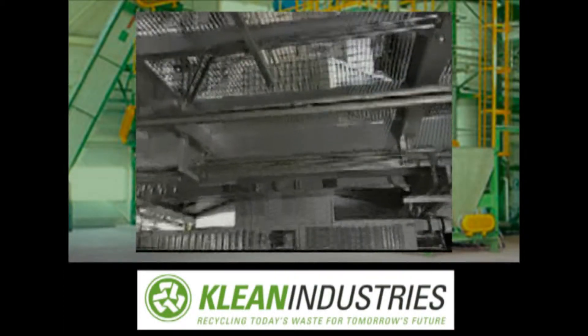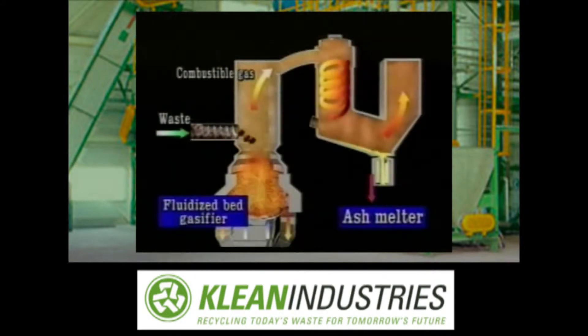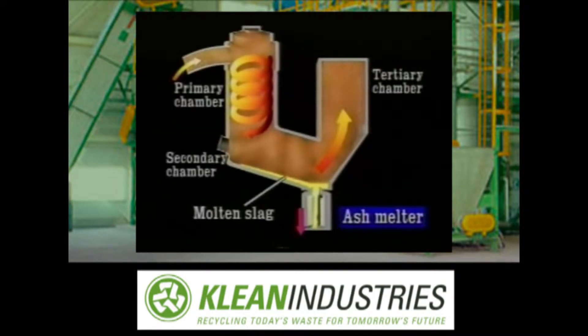The gas from the fluidized bed gasifier is led into the ash melter, where it is combusted at a low air ratio to reach temperatures as high as 1,350 degrees Celsius to melt the ash into vitreous slag. The ash melter consists of the primary chamber, inside which the ash entrained with gas is collected on the chamber wall by cyclonic motion, the inclined type chamber for collecting slag in the secondary chamber, and a tertiary chamber for the complete combustion of gas. Gas whirls along the ash melter wall while burning at 1,350 degrees Celsius.